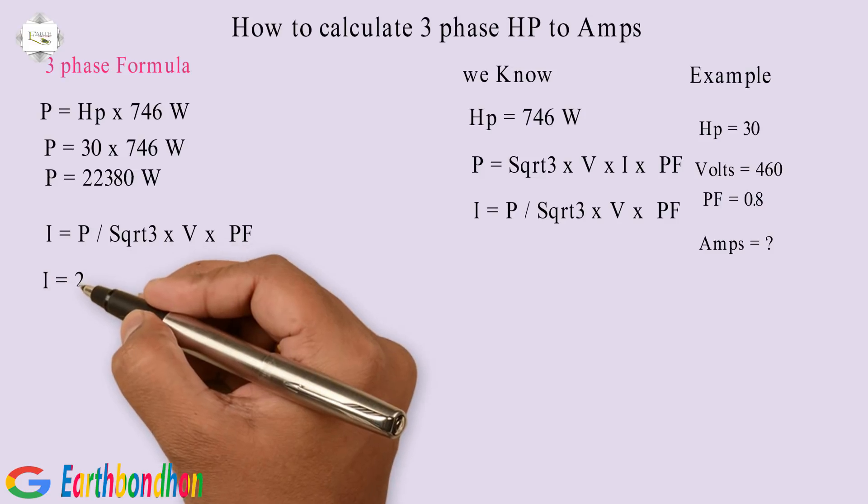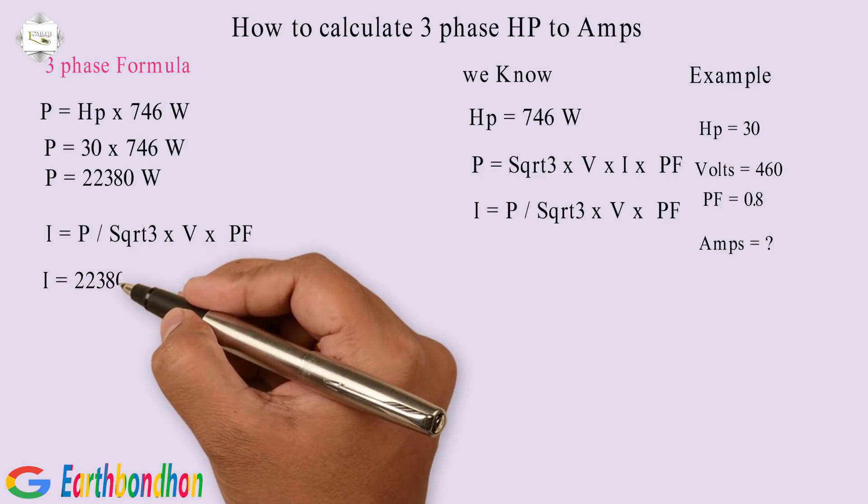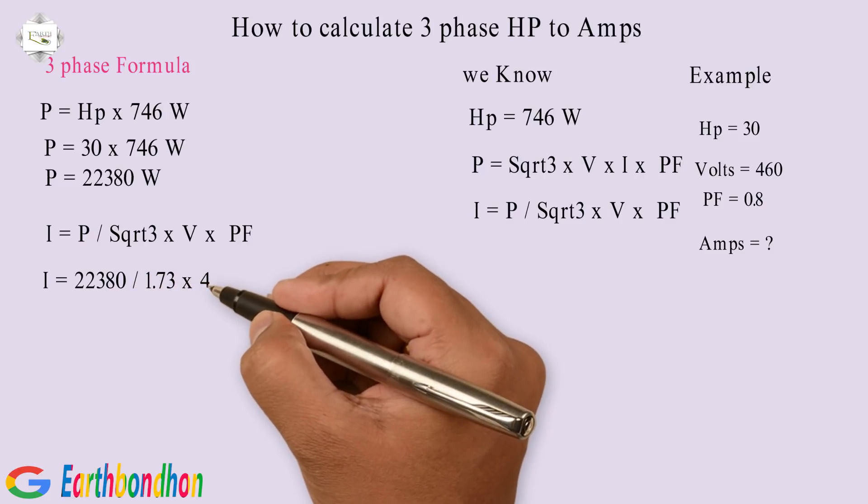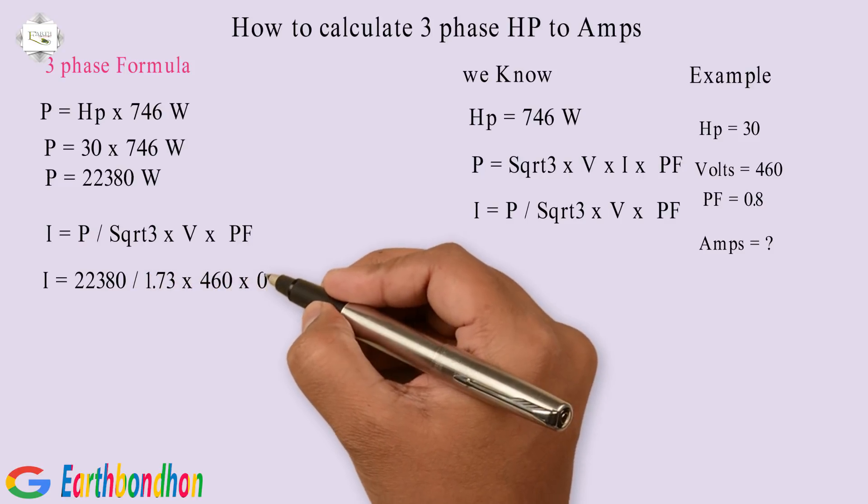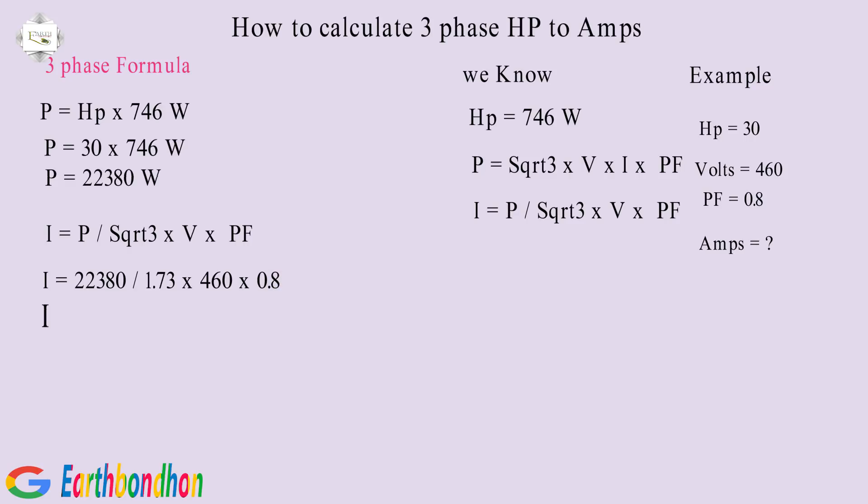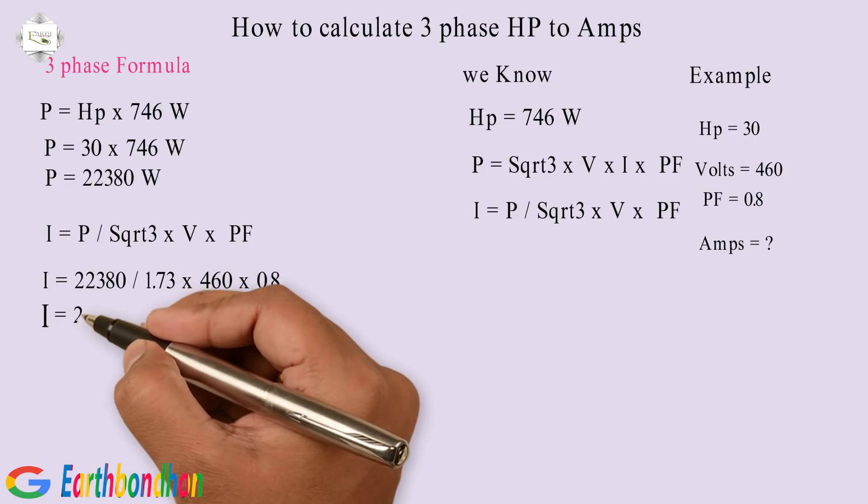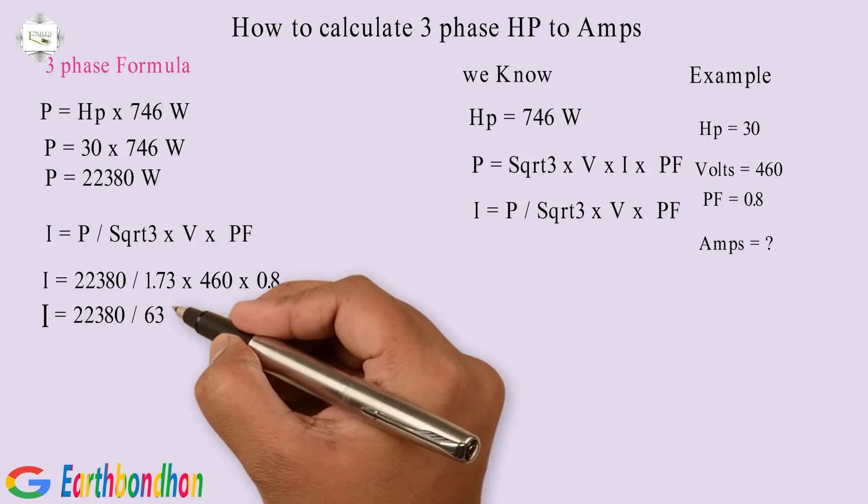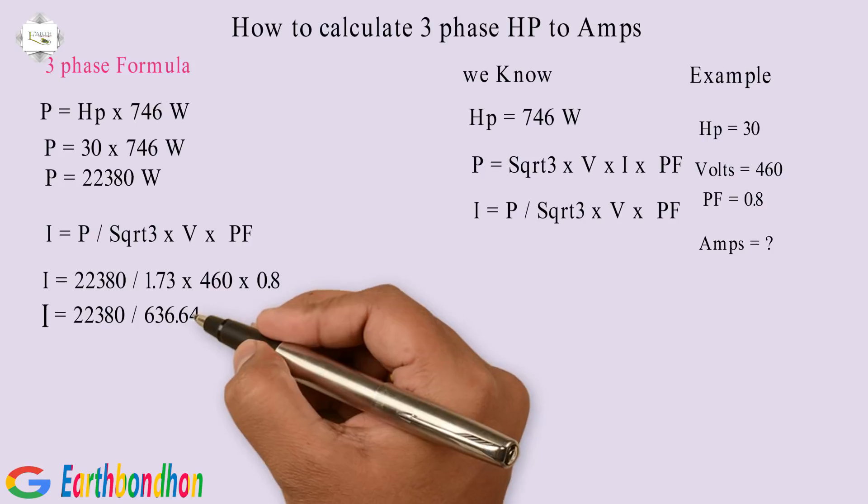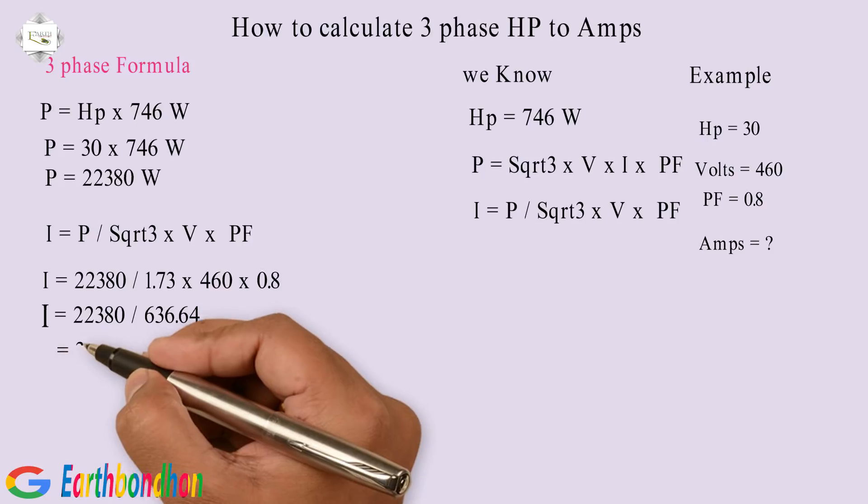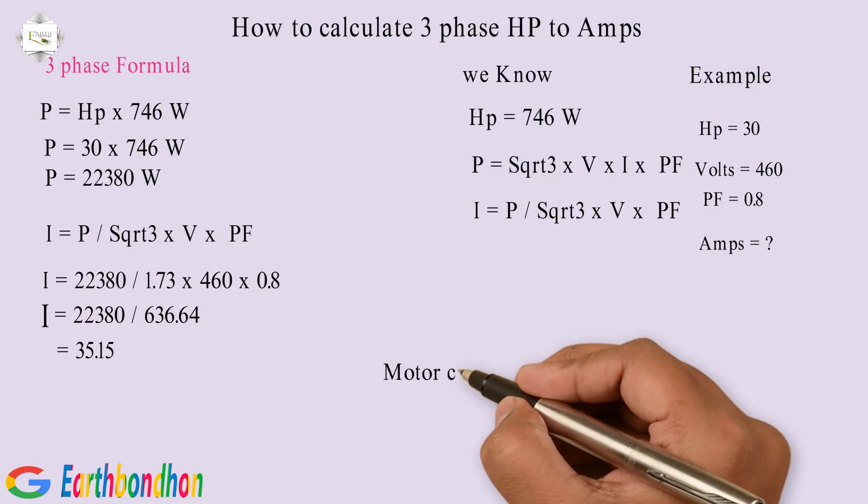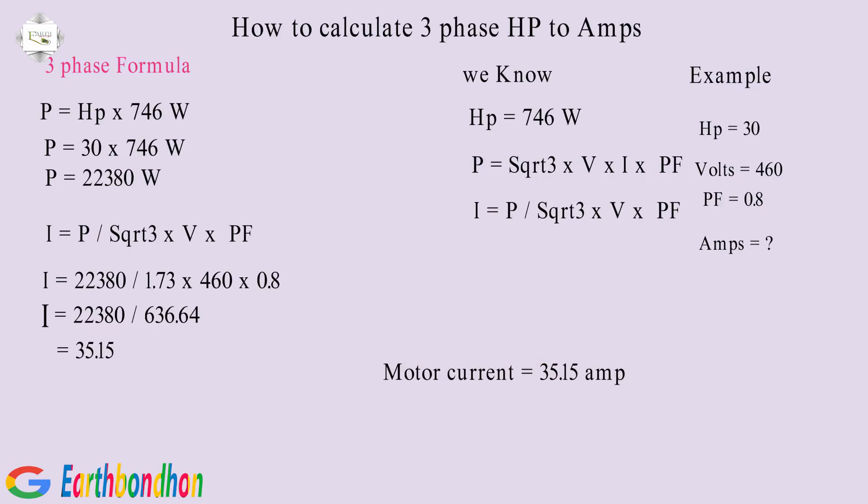I equals 22,380 division 1.73 multiplication 460 multiplication 0.8, equals 22,380 division 636.64, equals 35.15. Motor current equals 35.15 amps.